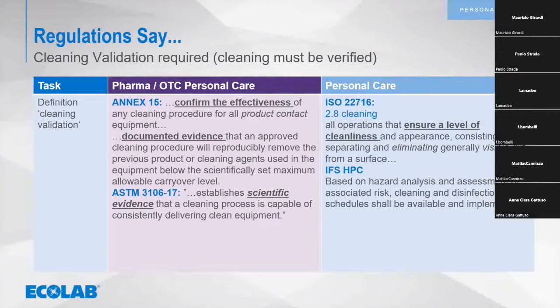This is why there is always a lot of documentation needed, and that is sometimes even true for over-the-counter products you want to bring into the US market. The ASTM guide outlines that there should be scientific evidence that a cleaning process is capable of delivering clean equipment. These kinds of definitions of cleaning validation exist, going from documentation just to the level of cleanliness you want to ensure. This is the span width, I would say, the minimum or maximum point you can use for your validation, what you want to set up for your site.